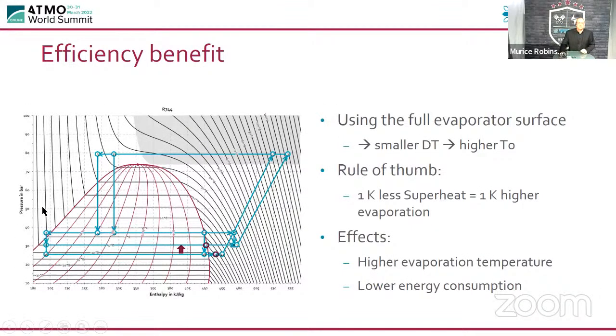Having a look at the p-h chart, you can see that just increasing the full evaporator surface creates a smaller DT, and there's a higher temperature output. And the rule of thumb for this whole thing is 1 K less superheat gives you 1 K higher evaporation. So when you drop your superheat, you can increase your suction temperature. As the one goes down, the other goes up. And the closer you get those two together, the better you're going to have on your energy saving. So the effect is a higher evaporation temperature and lower energy consumption.